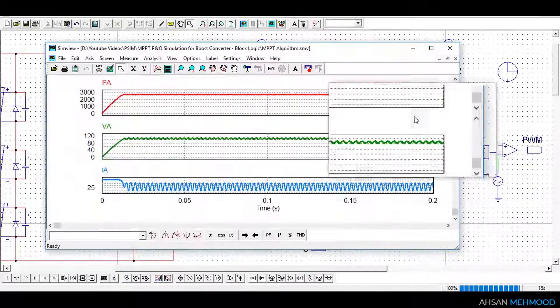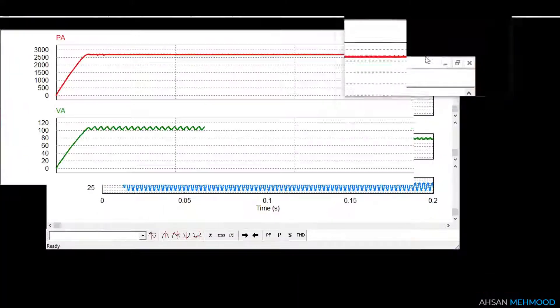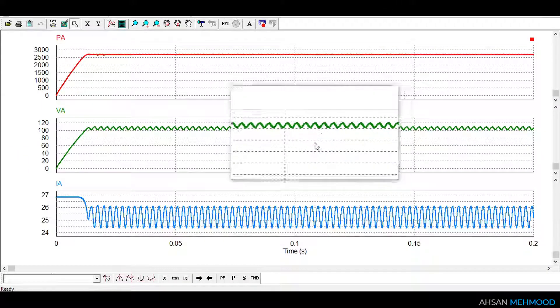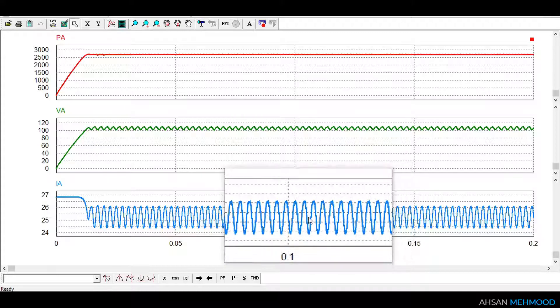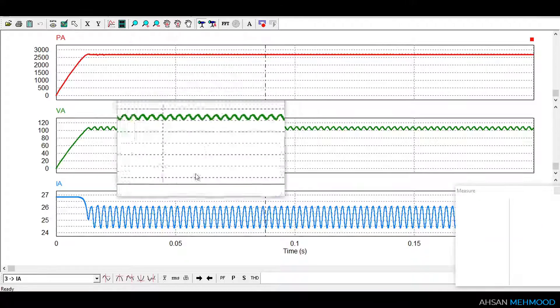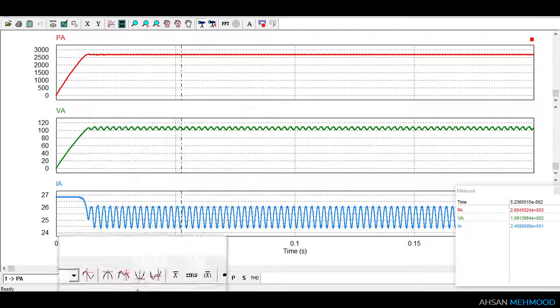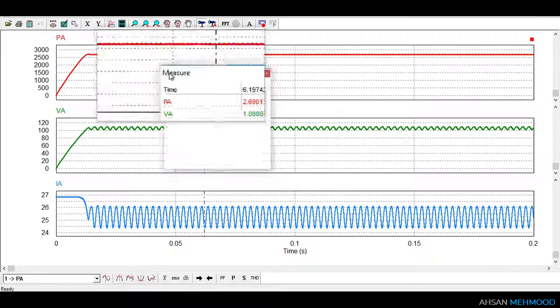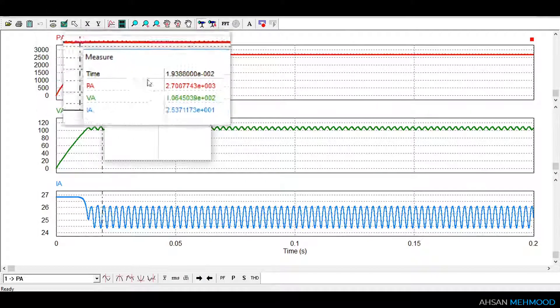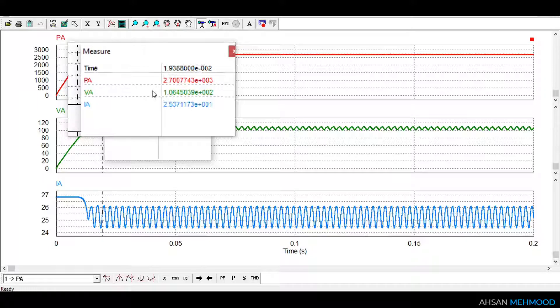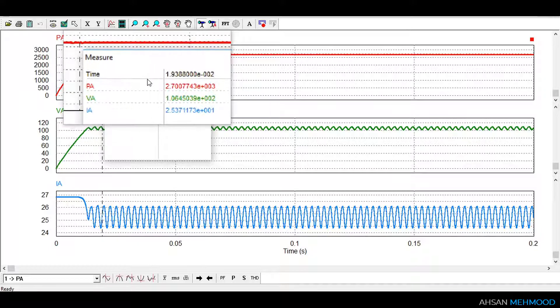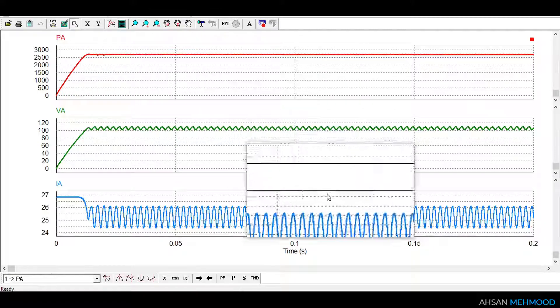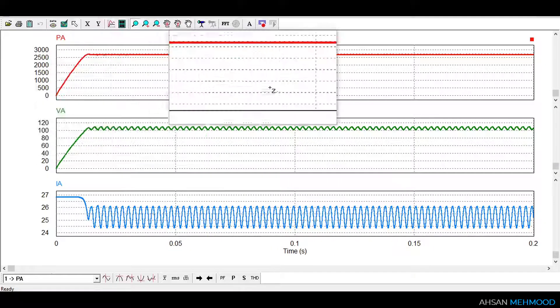These are the graphs of array power, voltage and current. Array power is shown in red color, array voltage is shown in green color and array current is shown in blue color. As you can see array is operating at around 2700 watt which is the maximum power point of the PV array at standard testing conditions. At this point array voltage and current are 106.4 volt and 25.4 ampere respectively. This shows that our P&O control is working perfectly.